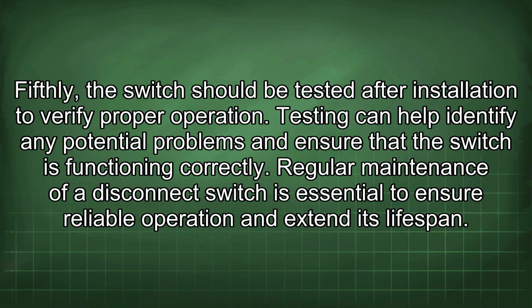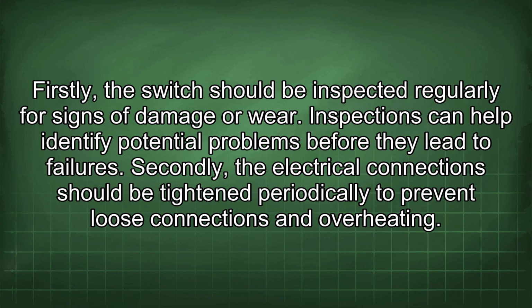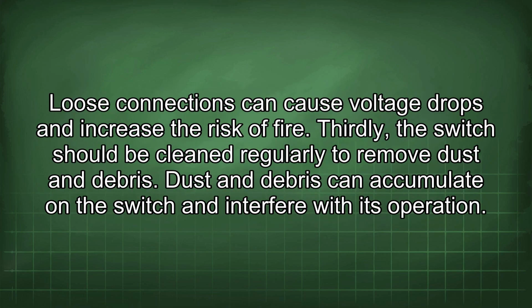Regular maintenance of a disconnect switch is essential to ensure reliable operation and extend its lifespan. Firstly, the switch should be inspected regularly for signs of damage or wear. Inspections can help identify potential problems before they lead to failures. Secondly, the electrical connections should be tightened periodically to prevent loose connections and overheating. Loose connections can cause voltage drops and increase the risk of fire. Thirdly, the switch should be cleaned regularly to remove dust and debris. Dust and debris can accumulate in the switch and interfere with its operation.